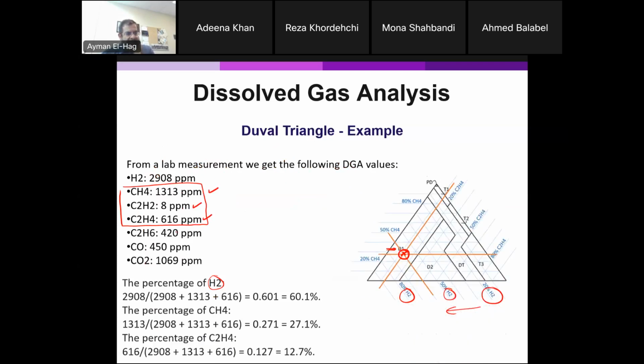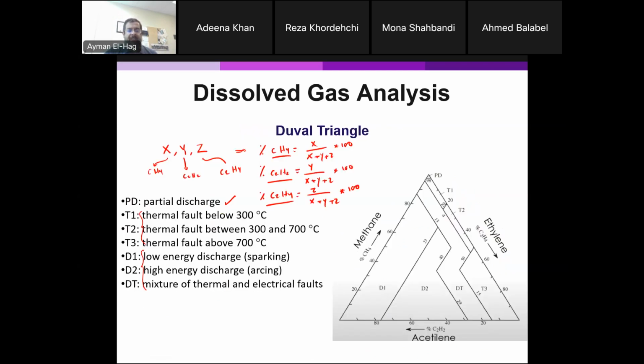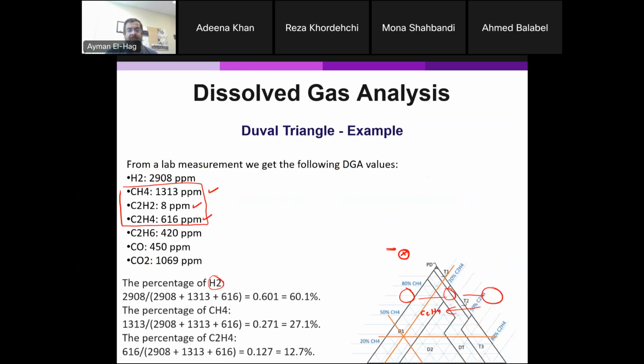Okay, so let me check this point. The ethylene here is 616. Even if you take the H2 instead and use it in place of the C2H2, you will find that it is very, very close to this as well. Okay, but I will check and come back to you. I might send an email to correct this, or I will change the slides. Anyway, let's go back here. The point of intersection here is the point that reflects where the intersection is. It has to be in one point. So this is in D1. D1 is a low energy discharge, sparking that happened in the transformer. Okay, so that is how we can use the Duval triangle.